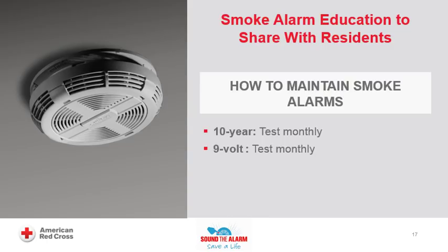Remember, regardless of whether an alarm is hardwired, 10-year or 9-volt, all smoke alarms should be tested monthly to ensure that they're in working order. All smoke alarms should be replaced after 10 years or earlier if needed. This includes hardwired units.